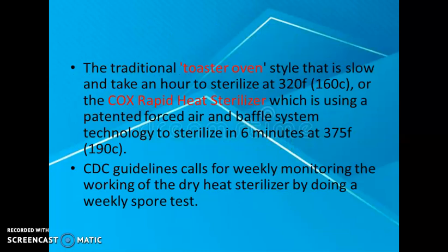The traditional toaster oven style is slow, and it takes an hour to sterilize at 320 °F. Or the Cox rapid heat sterilizer, which uses a patented forced air and baffle system technology to sterilize within 6 minutes at 375 Fahrenheit. CDC guidelines call for weekly monitoring of the working of dry heat sterilizers by doing a weekly spore test. Usually this spore test we do in hot air ovens also.